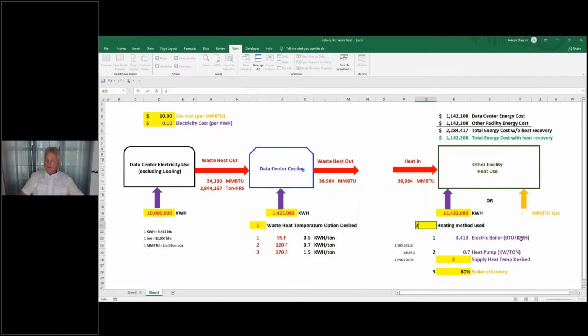But suppose you're doing that, then the value of that energy might only be $270,000. The point is, for another facility to use the waste heat that the data center is throwing away has a value of $250,000 to $500,000. So the question is, would it be cost effective over 30 years to find a way to get this waste heat from the data center to this other facility?